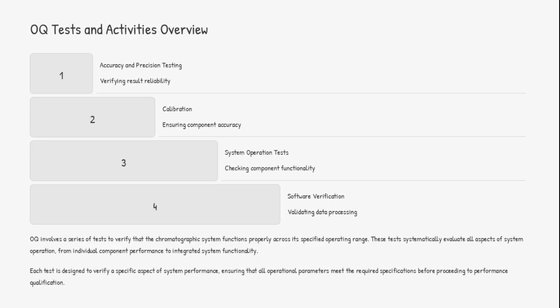OQ tests involve a series of activities to verify that the chromatographic system functions properly across its specified operating range. These tests include accuracy and precision testing, calibration, system operation tests, and software verification, ensuring all operational parameters are met before proceeding to performance qualification.